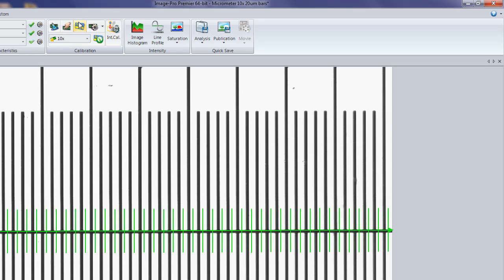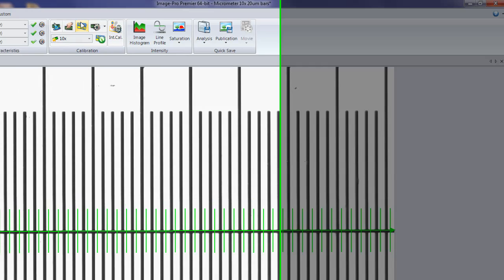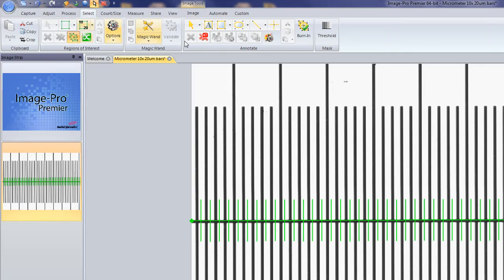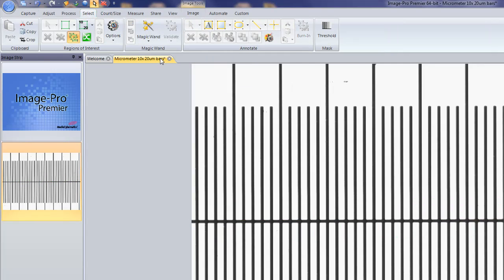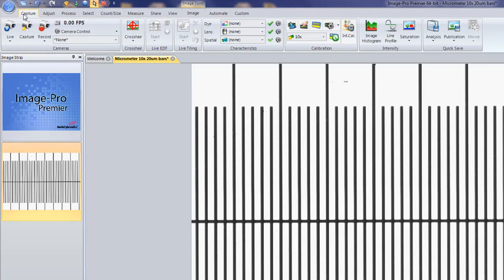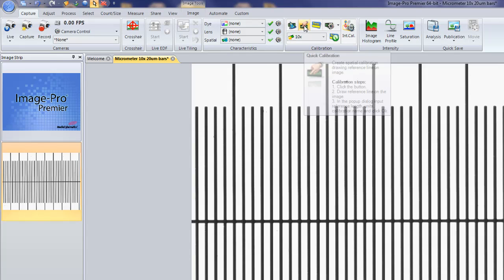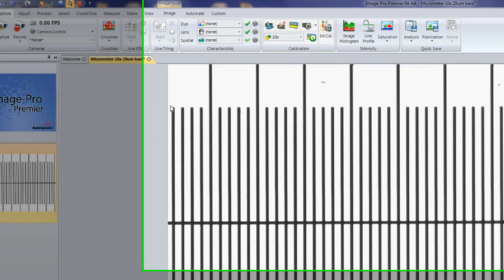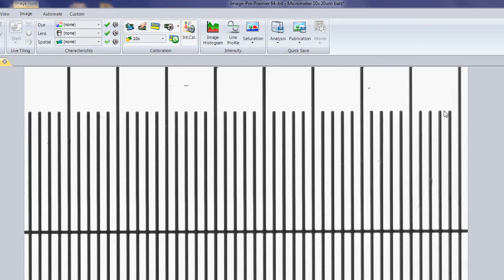I'm going to turn my marker bar off for a minute, and I'm going to get rid of this annotation to show you how to create another spatial calibration using the other method. In this case, I'm just going to go to the Select tab and delete my annotation. Going back to the Capture tab, the second method is to draw a line from one point to another and tell the program what that distance is. That will create the calibration determining pixels per micron in this case. So let me do that.